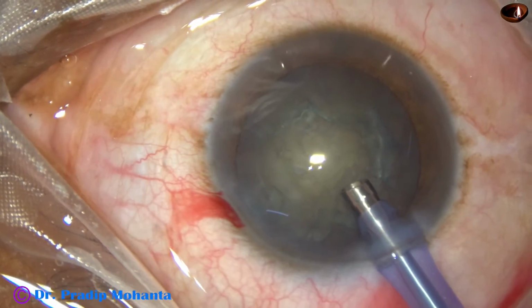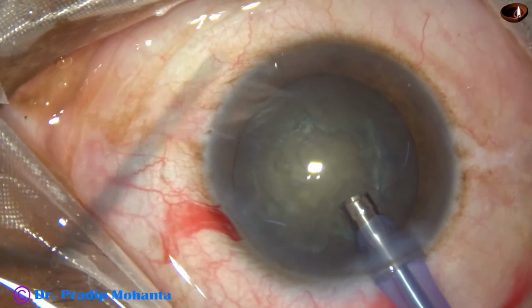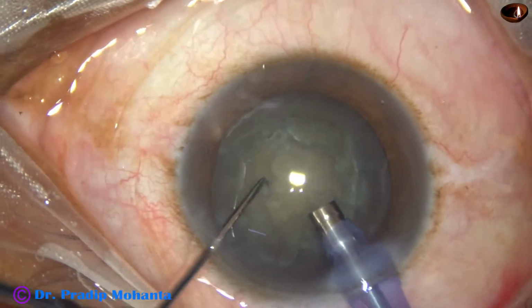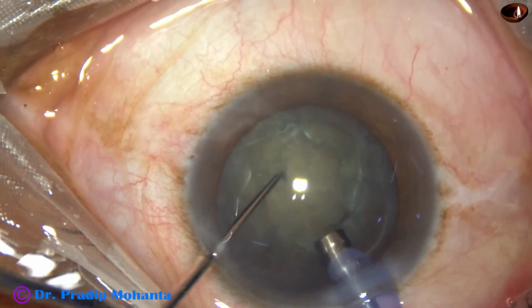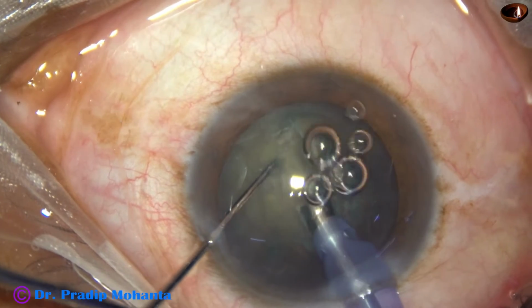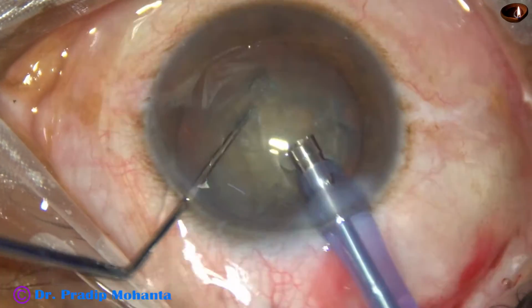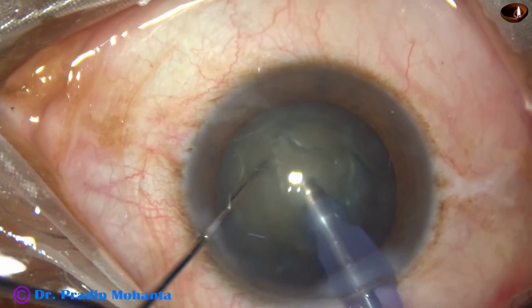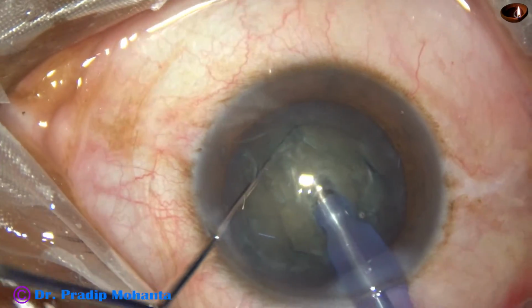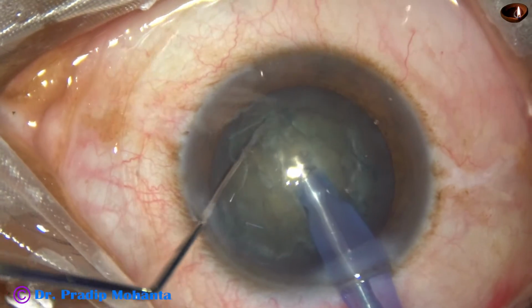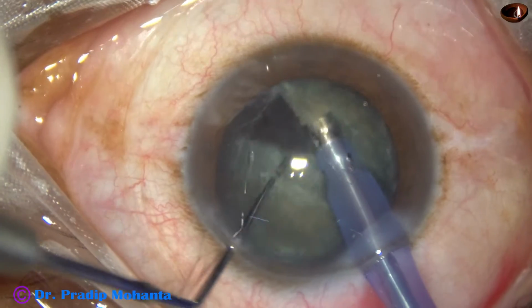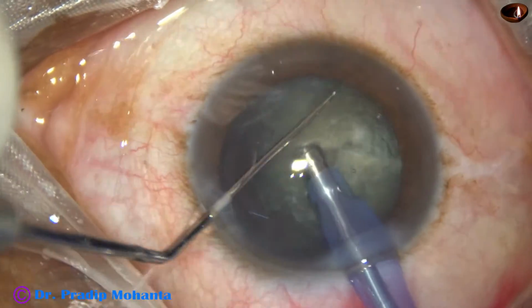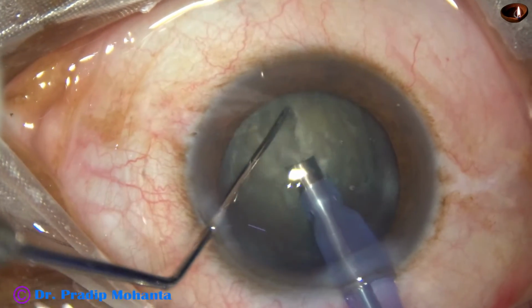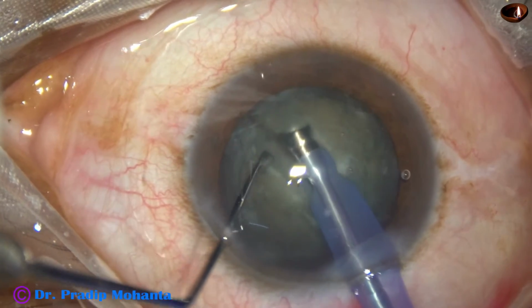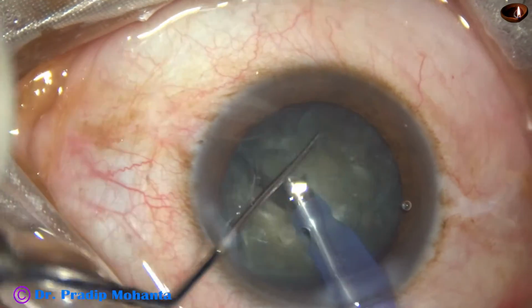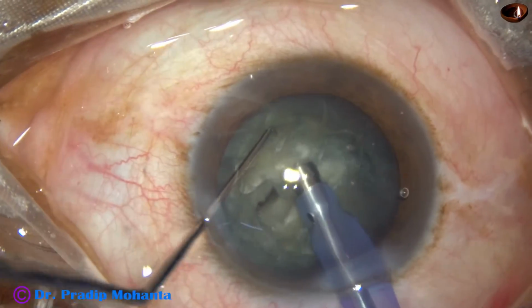in the occupulse mode, that means occlusion pulse mode, where when the tip is occluded, the machine goes to pulse mode. If the tip is not occluded, it is in the continuous mode. The ultrasonic delivery is continuous, and this is a very nice mode in this machine, and it gives very good followability of the pieces.